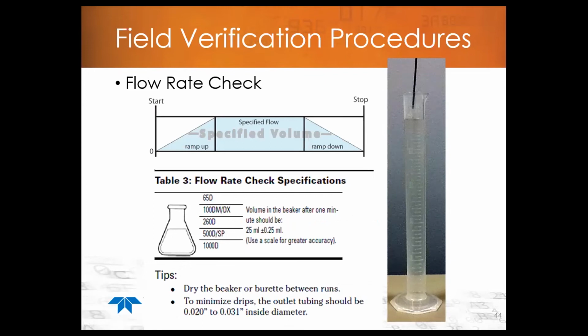It does indicate here that you can use the dispense mode. Not all pumps, depending on the age of your controller, have a dispense mode. If you do, you can use the dispense mode to check the flow rate. If not, then you'll just have to put the pump in the constant flow mode, enter your flow rate of 25 mils a minute, and then just let it run for 1 minute and collect that volume into a graduated cylinder.